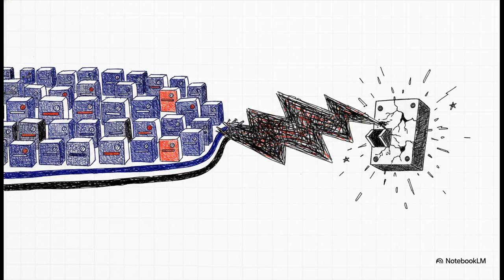So the absolutely crucial point here is that adding a single generator isn't just about plugging in more power. When you add that 5th machine, every single existing breaker on that switchboard, even the ones installed years ago, needs to be aggressively rechecked against this new higher fault level. If the new cumulative fault current exceeds what your older breakers were designed to survive, a short circuit is going to blow them apart instead of safely interrupting the flow.